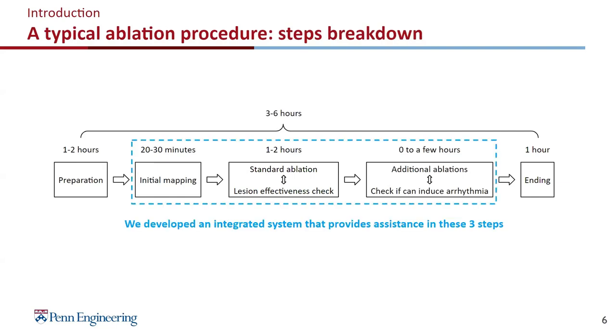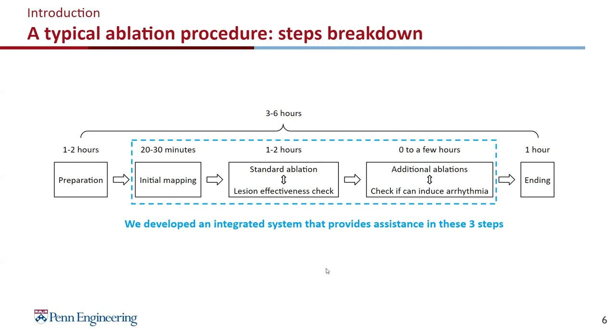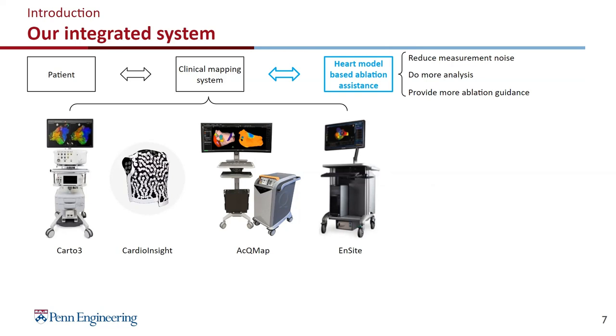We developed an integrated system that provides assistance in these three steps. There are many companies making different types of mapping systems — four different types shown here, all similar. What they do is take measurements from the left atrium and interpolate them into the atrium geometry and display it as a color map. What we add is that we integrate the heart model to this system. The advantage is we can reduce measurement noise, do more analysis, and provide more ablation assistance with our heart model.